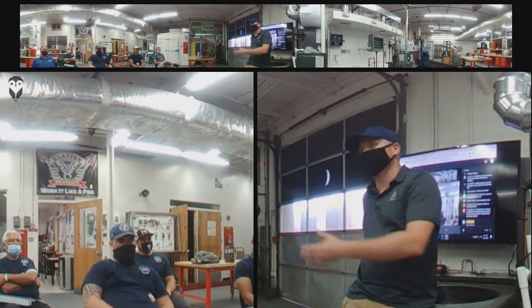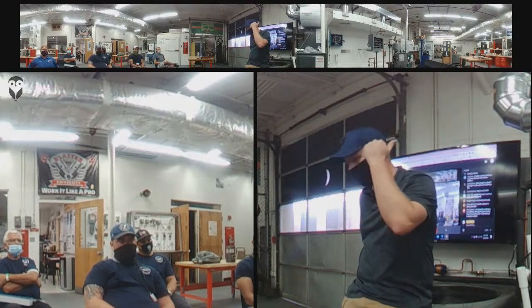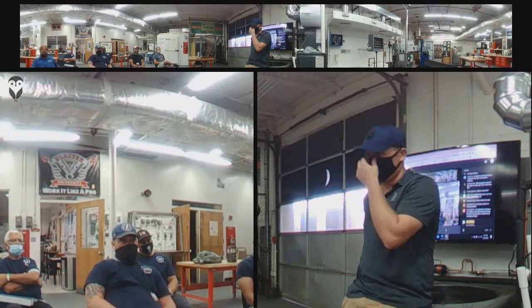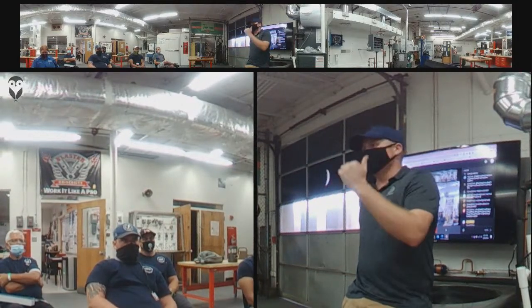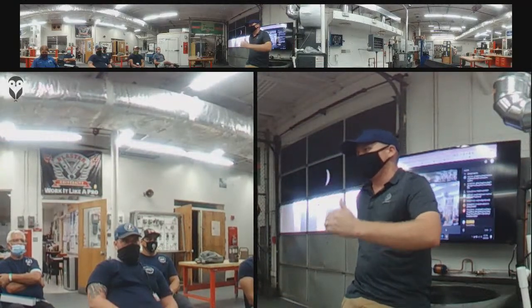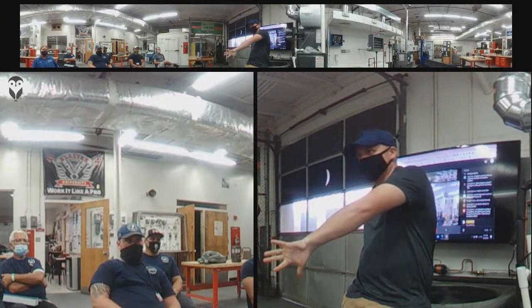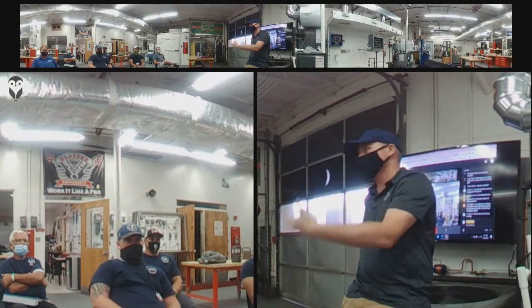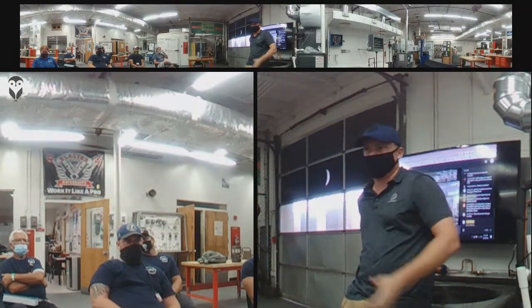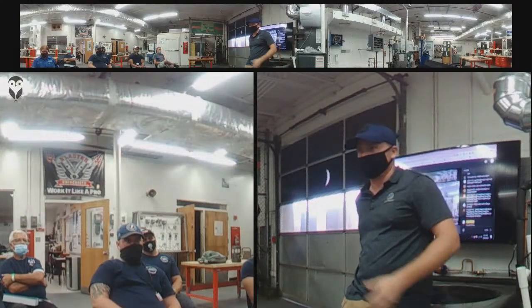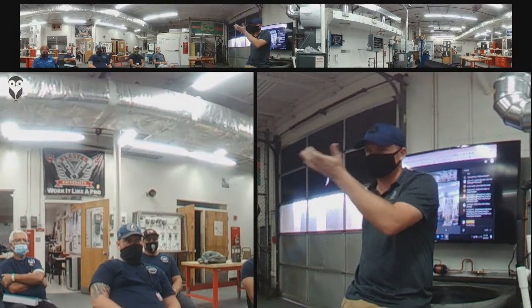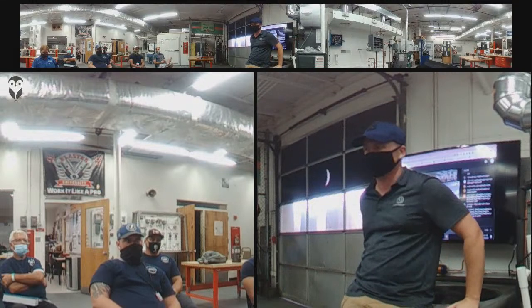Yeah, and that's something we've talked about before. In terms of diagnosing boards or any sort of control, good technicians don't jump to the thing they don't understand and say, oh, the board's bad. They look at everything else that's connected to it to see if it's something else. A lot of times you see boards get condemned because of failed pressure switches or wiring problems, things like that. So it's good that you went through that entire process.